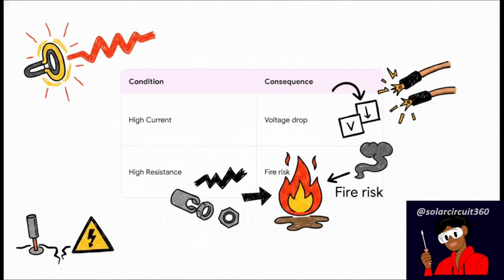Higher current produces more voltage drop, heats up your cables, and stresses out the connectors. Higher resistance, which is often caused by just a bad crimp or a loose lug, produces more heat, lowers your efficiency, and drastically increases the risk of fire. And poor grounding? Well, that produces fault clearing problems and severe shock hazards. These are the literal physical manifestations of invisible forces. If you don't actively measure for them, you won't know they're there until you start smelling melting insulation.